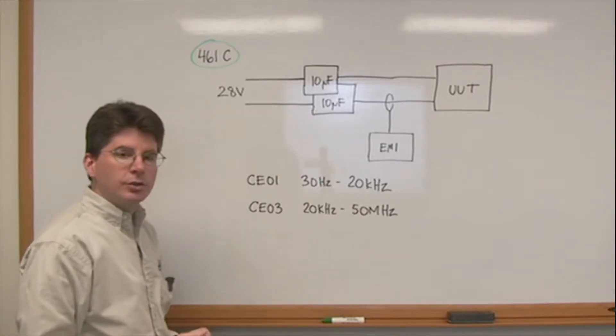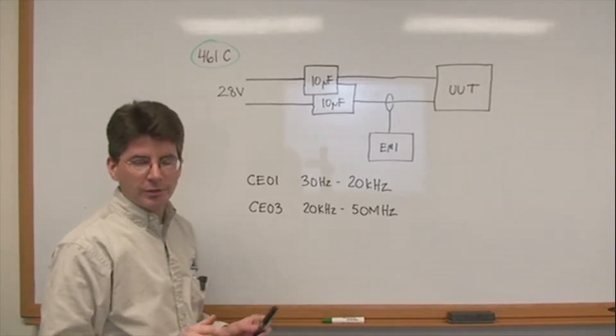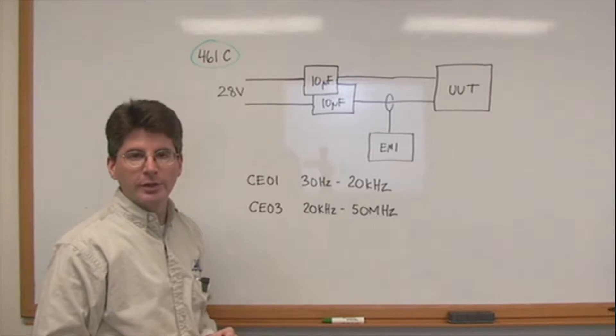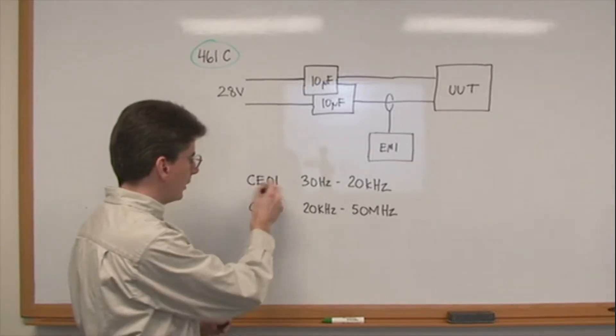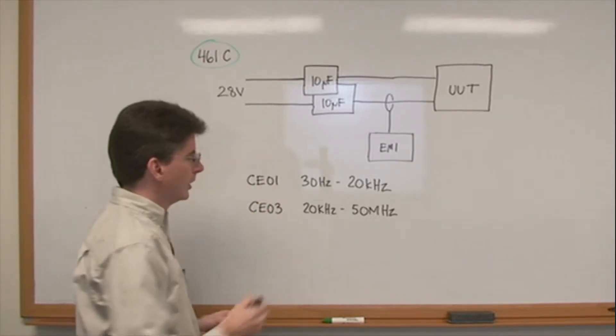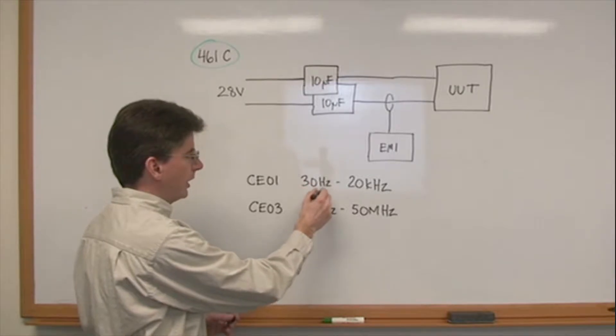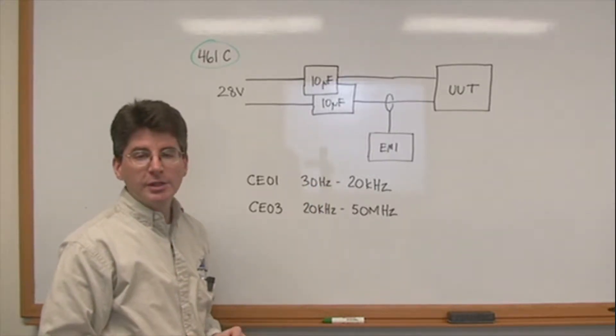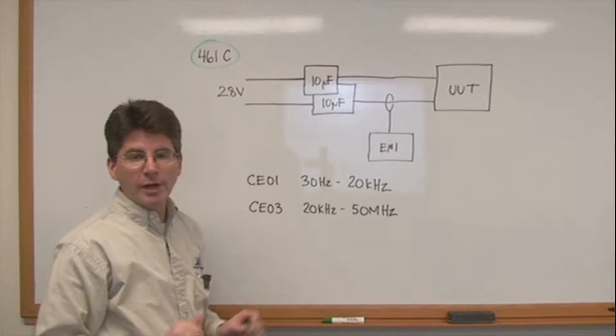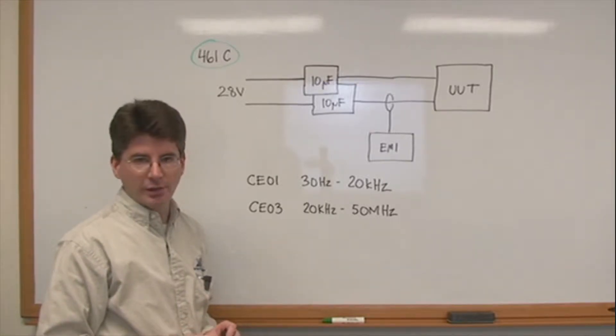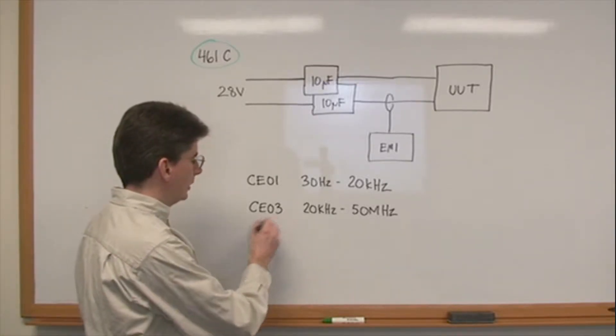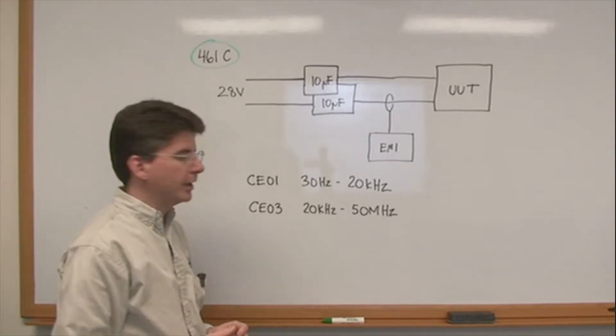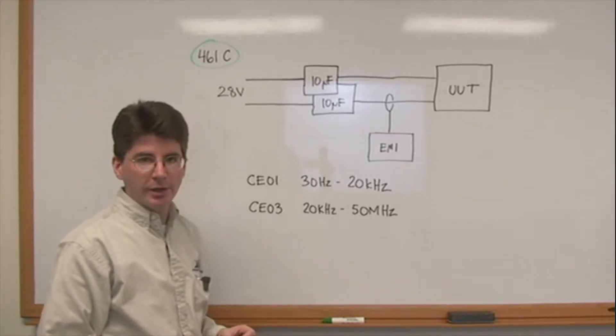There are two conducted emissions requirements in 461C which are relevant to power converters. The first is CE01, which is in the frequency band 30 hertz to 20 kilohertz. VPT's DC-DC converters do not emit any noise in this range. The second is CE03, which is in the range of 20 kilohertz to 50 megahertz. This is where we will primarily be concerned.